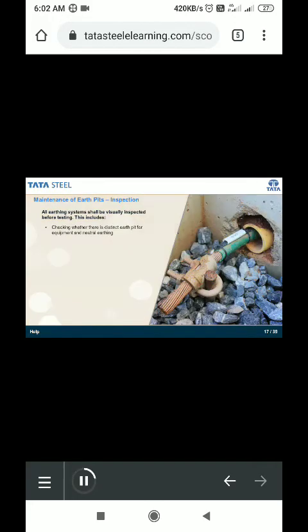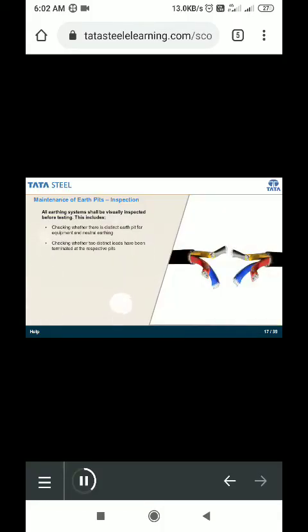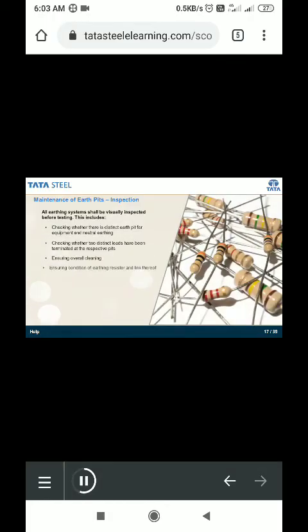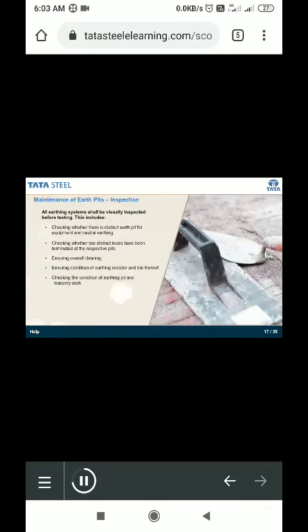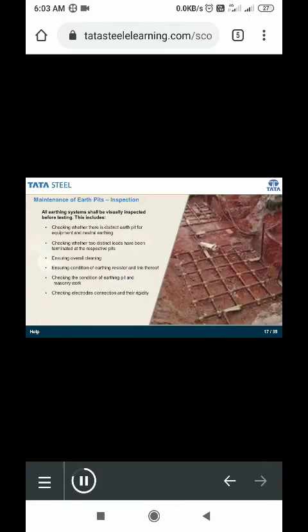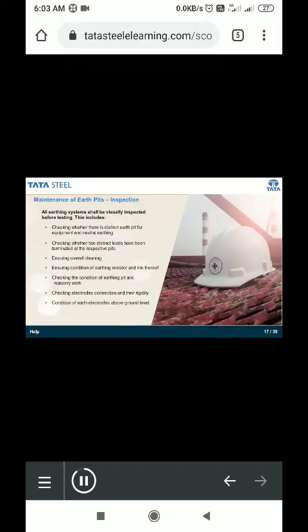In the inspection phase, all earthing systems shall be visually inspected before testing. This includes checking whether there is a distinct earth pit for equipment and neutral earthing, checking whether two distinct leads have been terminated at the respective pits, ensuring overall cleaning, ensuring condition of the earthing resistor and link thereof, checking the condition of the earthing pit and masonry work, checking electrode connections and their rigidity, and the condition of earth electrodes above ground level. Once the voltage across the earth electrode and earthing lead is found to be below 5 volts, testing is done.